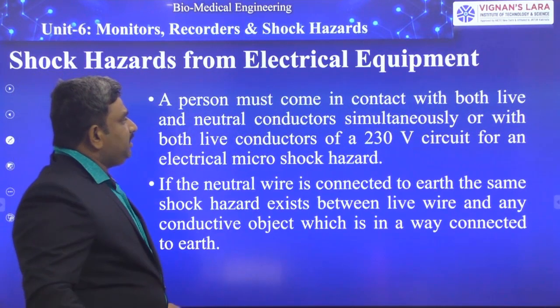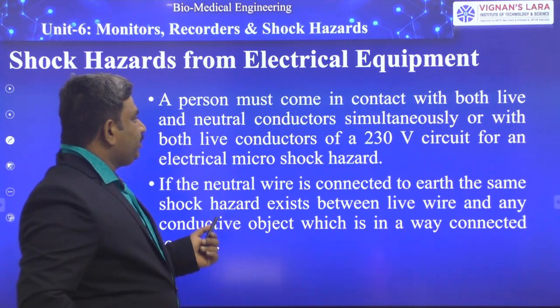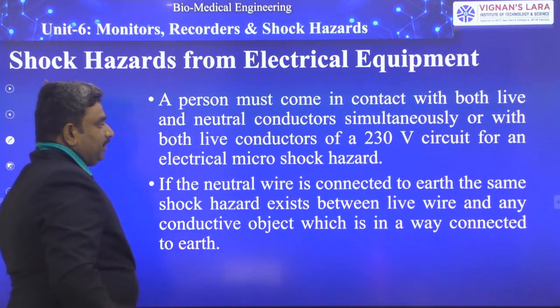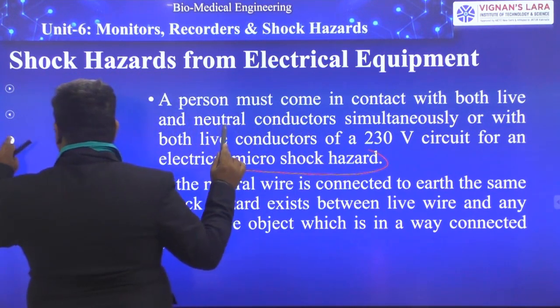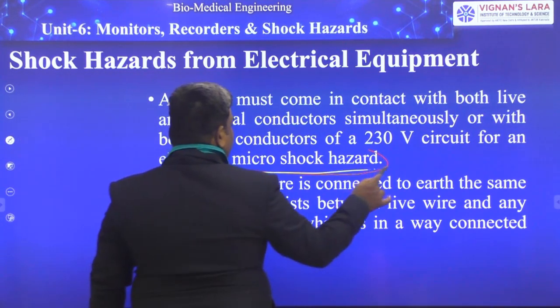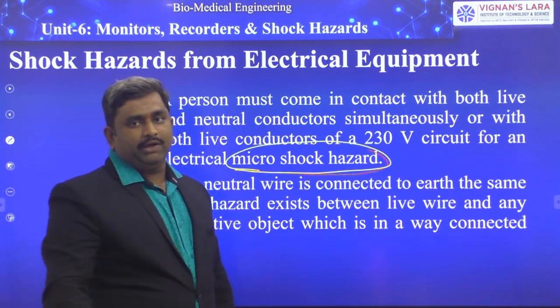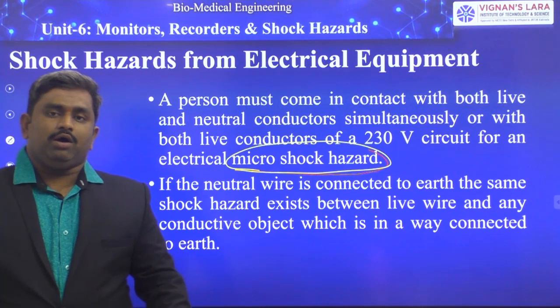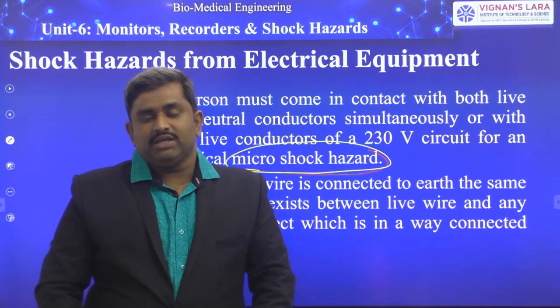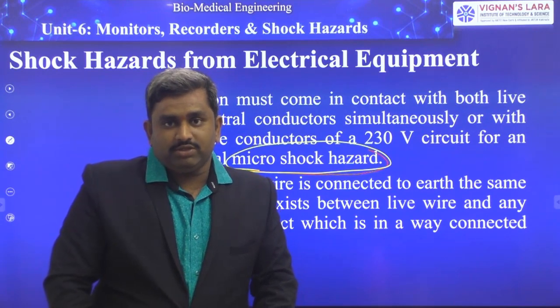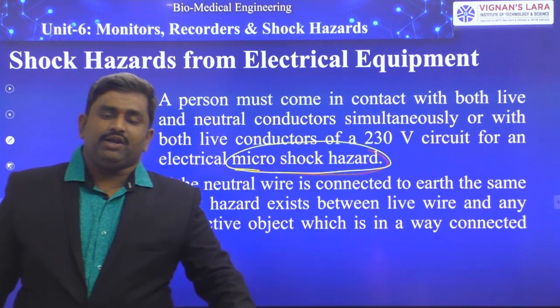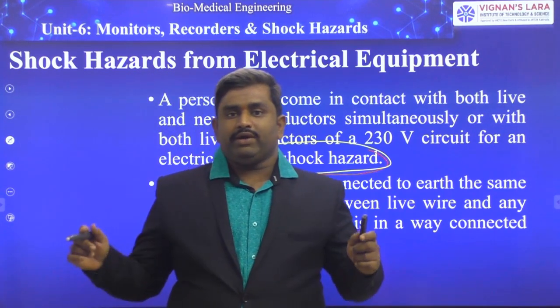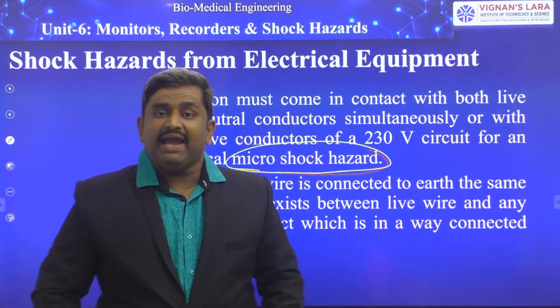A person must come in contact with both live and neutral conductors simultaneously for an electrical microshock hazard. In the previous classes we discussed microshock and macroshock. Microshock causes damage to internal organs when the phase and neutral conductors are connected internally to the body. For macroshock, the electrical conductors are connected to the external body surface. These two contacts coming to the external body surface cause macroshock.